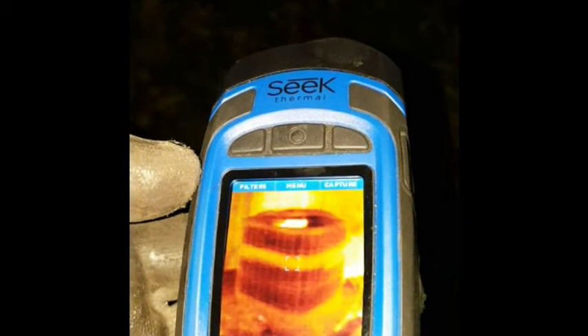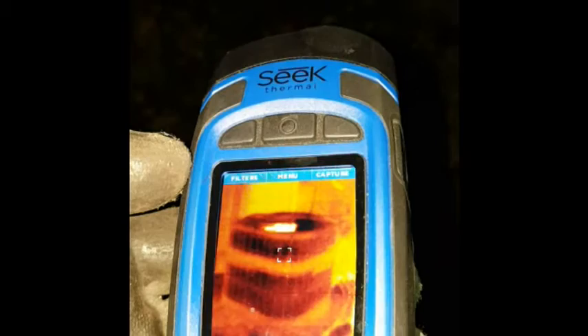Now we've got our pound of freon in. Sight glass — our subcooling is about 15 now. The sight glass cleared out; I probably put a little too much freon. And then you look on the thermal and this is more of a normal coil — it's three-quarters full, just got a little band right in the middle where there's no liquid refrigerant. So we're using a lot more surface area on that evaporator.